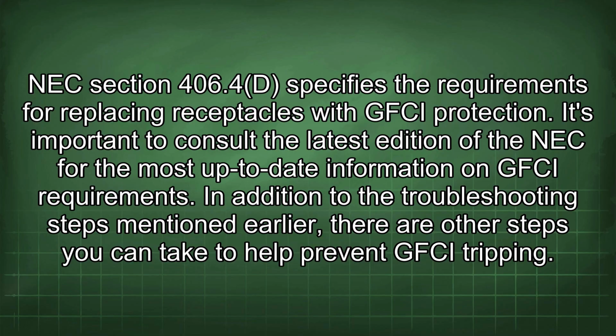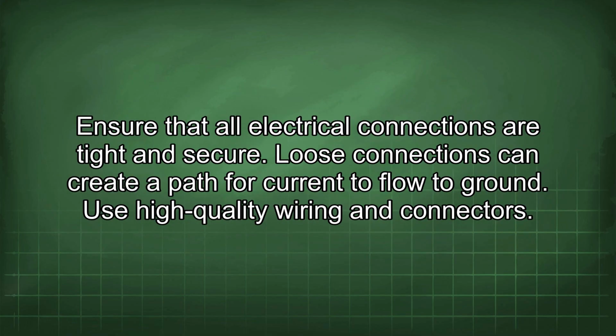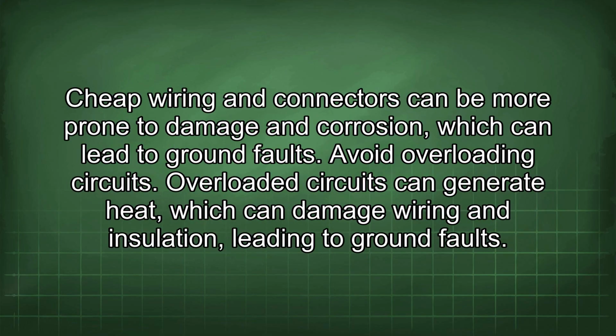In addition to the troubleshooting steps mentioned earlier, there are other steps you can take to help prevent GFCI tripping. Ensure that all electrical connections are tight and secure. Loose connections can create a path for current to flow to ground. Use high-quality wiring and connectors. Cheap wiring and connectors can be more prone to damage and corrosion, which can lead to ground faults. Avoid overloading circuits. Overloaded circuits can generate heat, which can damage wiring and insulation, leading to ground faults.